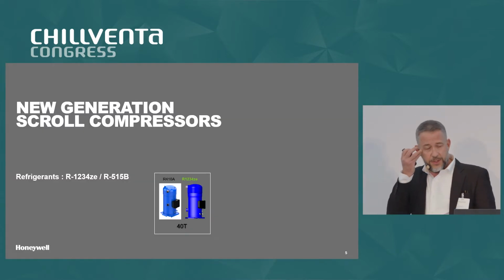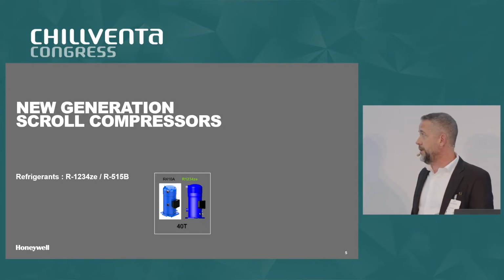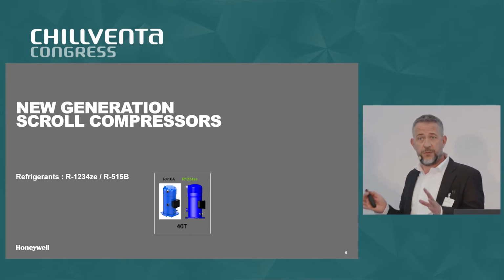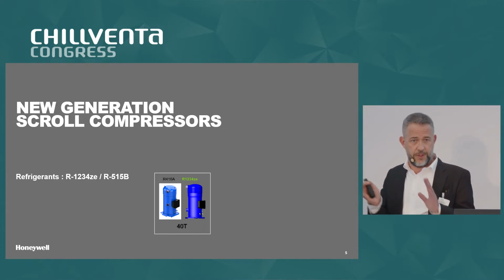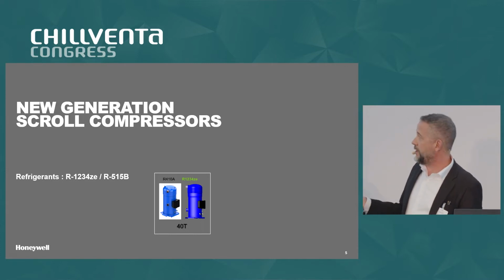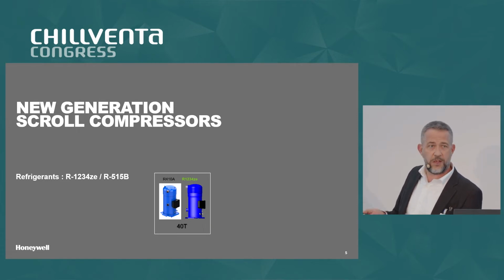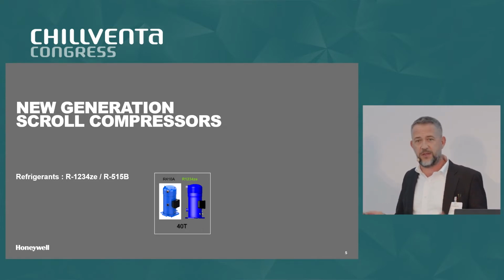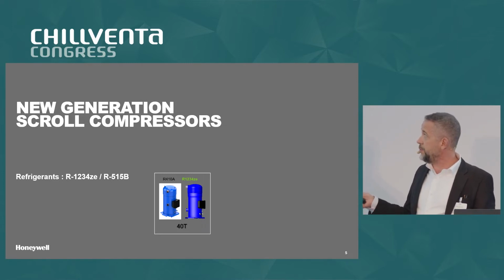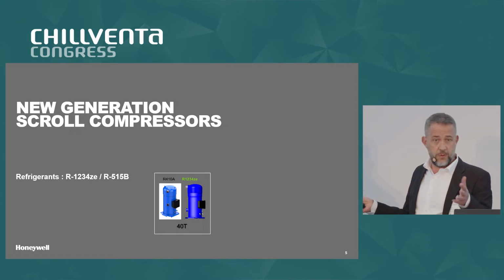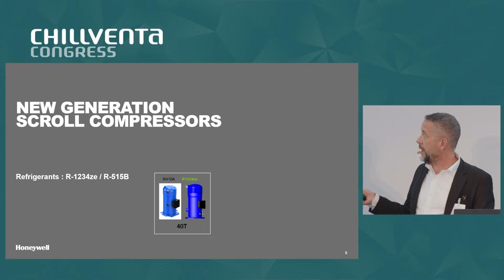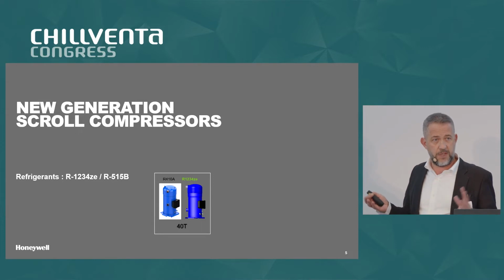So the next generation of scroll compressors, the long-term one, is running with these two refrigerants in the same compressor. Same compressor can do two refrigerants, no change. And I just wanted to introduce by the size, because when we start saying we go from high pressure to low pressure, people say, oh, but this is 3 times larger displacement, so you need much larger compressors. Absolutely not. This is the comparison between an R-410A 40-ton compressor, so 120 to 150 kilowatt, and a ZE 40-ton compressor. Exactly the same shape, same size.